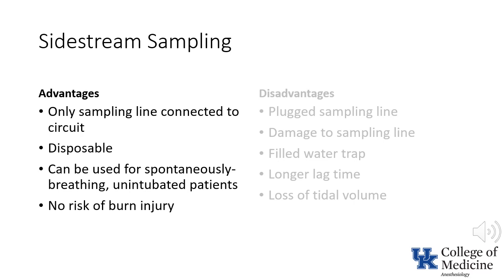One of the major advantages of sidestream sampling is that there are multiple different variations of nasal cannula which allow connecting a CO2 sampling line and measuring exhaled carbon dioxide in spontaneously breathing, non-intubated patients. And finally, because the measurement is performed away from the patient, no heating occurs at the site of the patient and there is no risk of burn injury.